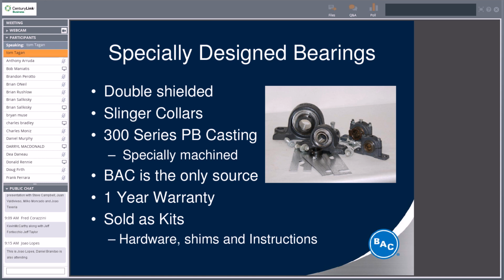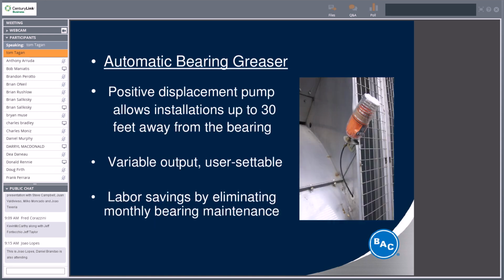Again, BAC put a little propaganda into this presentation about BAC being the only source. Again, most cooling tower manufacturers will provide parts for competitors. It's up to you guys who you get your parts from. This is an automatic bearing greaser that was mentioned earlier. It is an option. There is labor savings by eliminating having to do it manually every month. Obviously, you can set it, varying the output depending on what your specific installation requires.